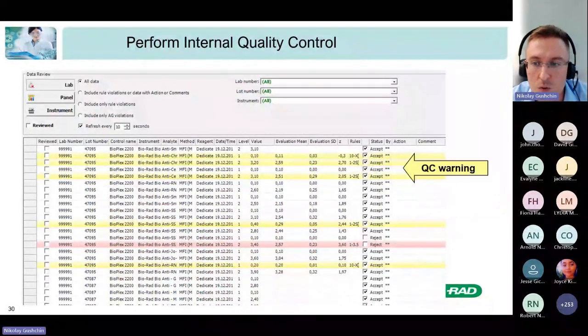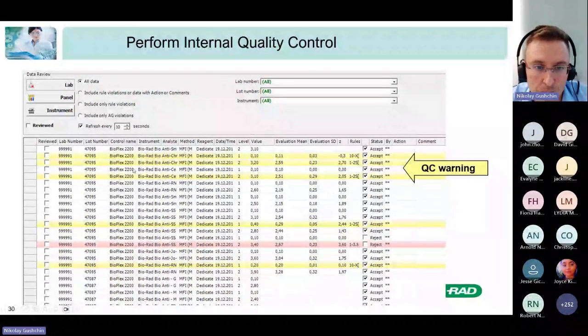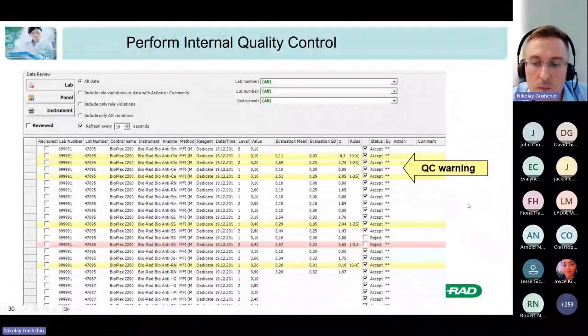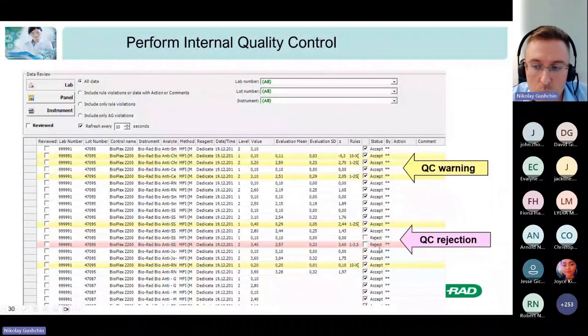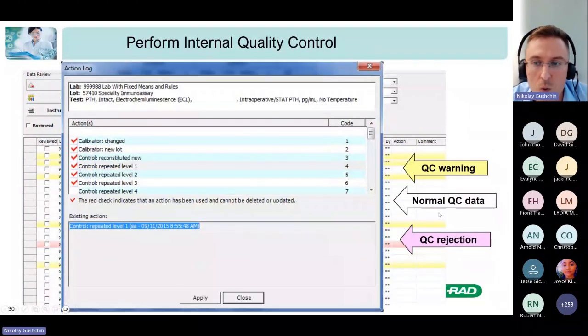I just want to quickly show you this report. You can see colors. Yellow color means that we have a QC warning, for example, and we can see the rules which were triggered with this warning. Red color means that we have a QC rejection, and white is for normal QC data. We also have columns with the action and comment, and if we did some troubleshooting or something happened in the lab, some event that can affect the results, we can also add this information to the software.